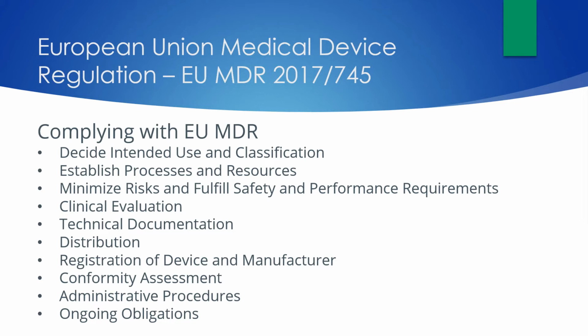Another requirement that is needed to comply with EU MDR is clinical evaluation. This will include having a clinical evaluation plan and report, along with clinical investigation documentation, and again, a post-market clinical follow-up plan. There also needs to be technical documentation, and this documentation should demonstrate how the device conforms to technical requirements, how it will achieve its intended purpose, that it's safe, and proper processes were followed to generate the data.